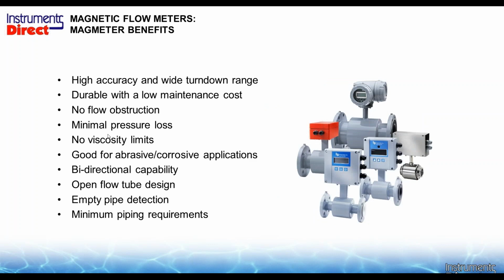So mag meters have some tremendous benefits in the world of measuring flow. Some of the neat features of this versus other types of technology are, of course, very high accuracy and a wide turndown range. They're very durable, and they have little to no maintenance. They really don't have any flow obstruction because most of them are pretty much a straight shot flow tube, so there's minimal or no pressure loss at all. They're not really affected by viscosity limits, and again, because they have really no obstructions, they're pretty good for most abrasive and corrosive applications. And there you have to monitor your materials of construction.